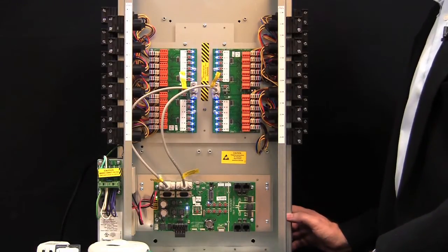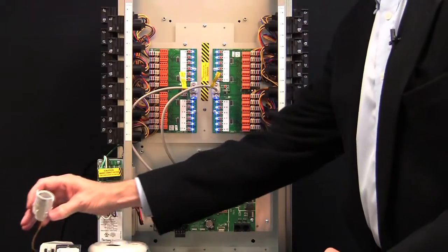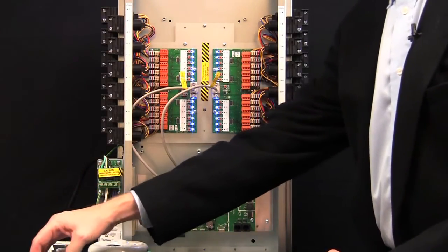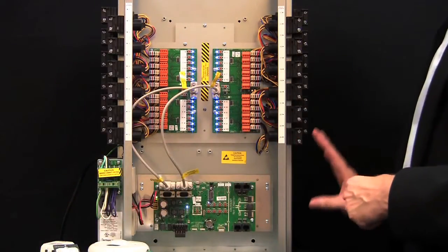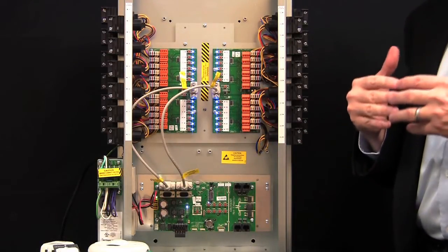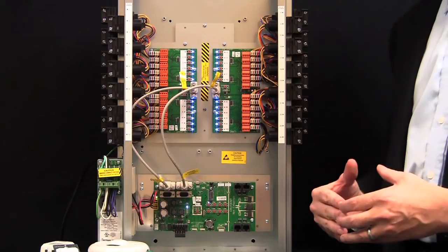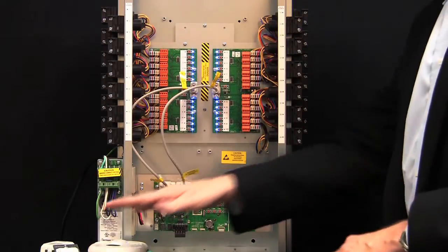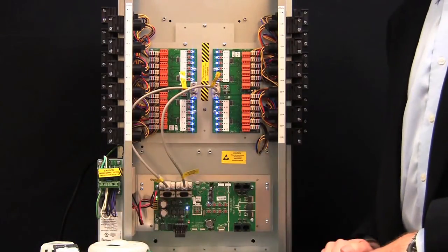The last schedule we're going to do is we're going to use a photocell, and we're going to use the astro function that's built into the panel, so that we can have a schedule so the lights will go on every morning based on the astro setting, but they'll go off every night when it goes below 50-foot candles.